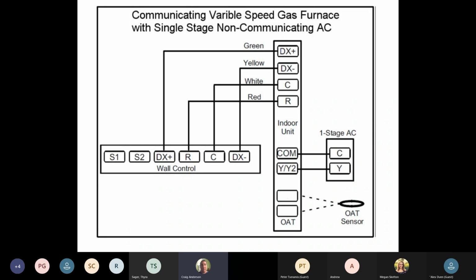If you go and you add an AC to a communicating system after the system's communicating, when you first hooked it up, there was no unit outside. You need to go back to the stat and you need the stat to tell it to relearn. So the stat is going to relearn itself. It's going to look for its indoor unit and it's going to look for an outdoor unit again. We start the process over if we've added something on or changed something.